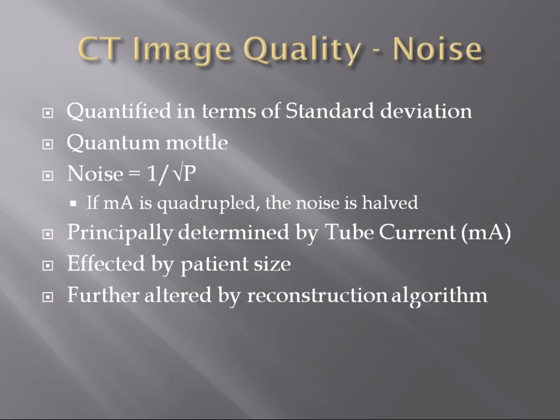Another parameter that will affect the MA and subsequently the noise is patient size. If we have a patient that is twice as big, a greater percentage of the x-ray beam is going to be attenuated before it hits the detector. As far as the detector knows, it's dealing with a reduced MA, which will increase the amount of noise. Furthermore, the reconstruction algorithm used to generate your images can also have an effect on perceived noise.